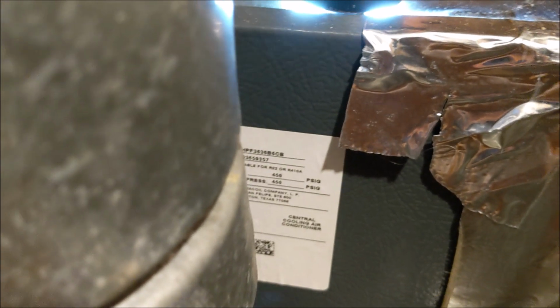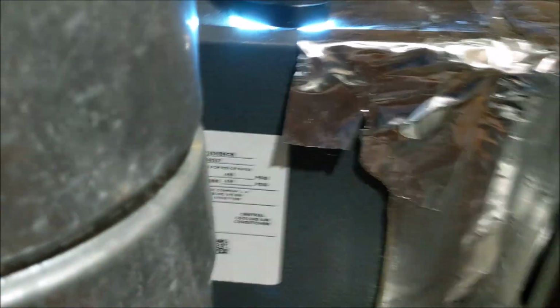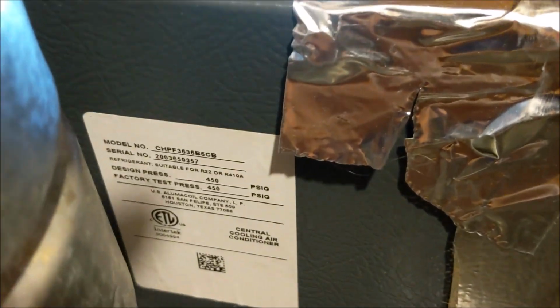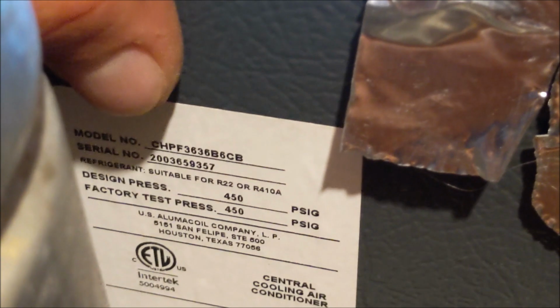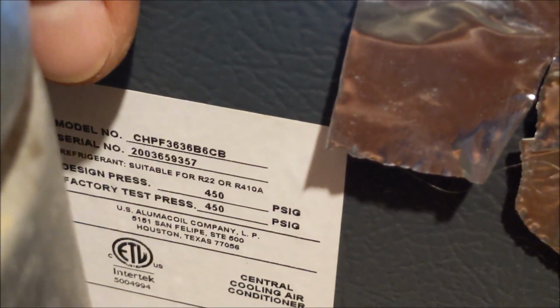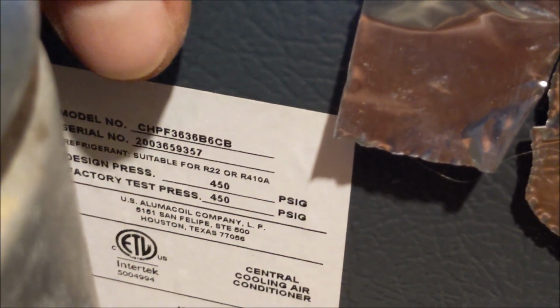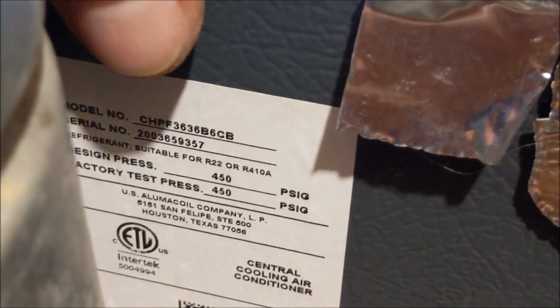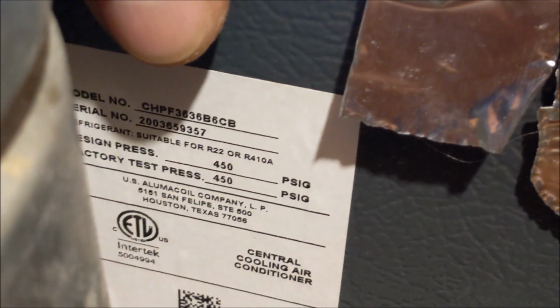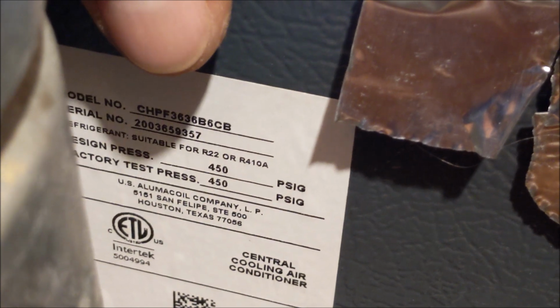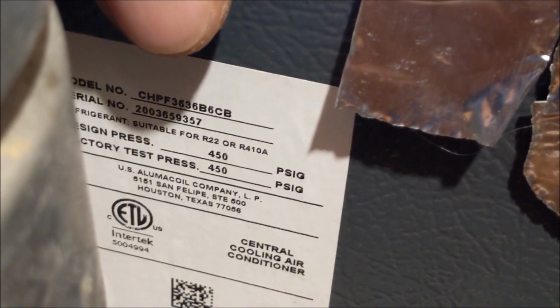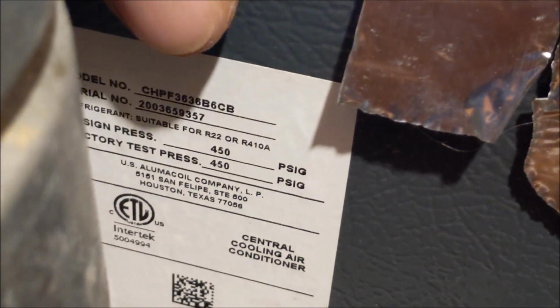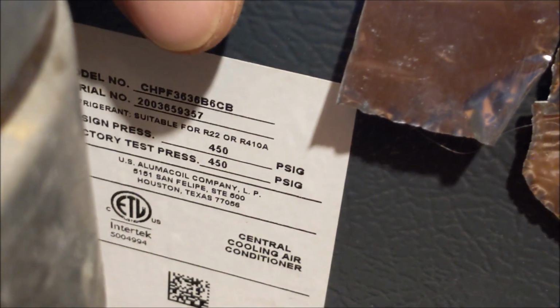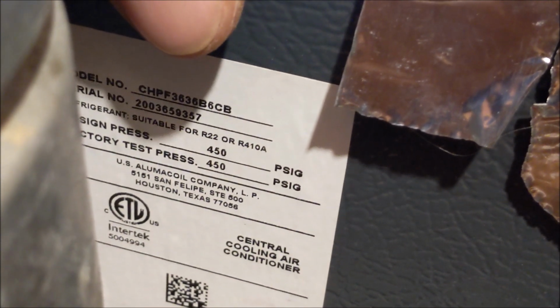Again, we're still upstairs in the attic where the water was in the pan. Come up the stairs, make a right. So we've got the evaporator coil, and if I can zoom in right here, we have a model number. The model number tells you the size of the evaporator coil. So we've got CHPF3636. That 36 right there means 3 tons, because 12,000 BTUs equals 1 ton, and 36,000 divided by 12,000 gives you 3 tons.